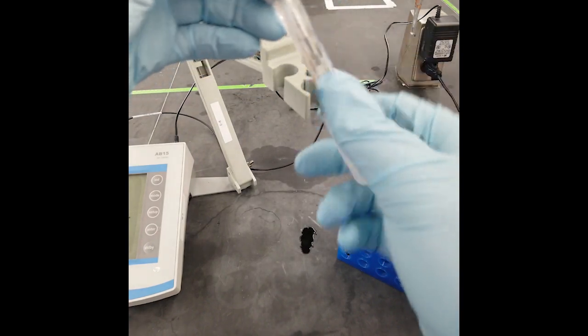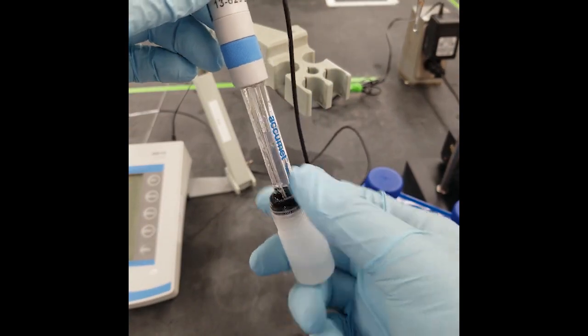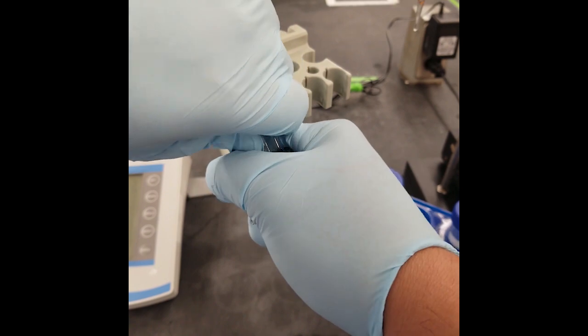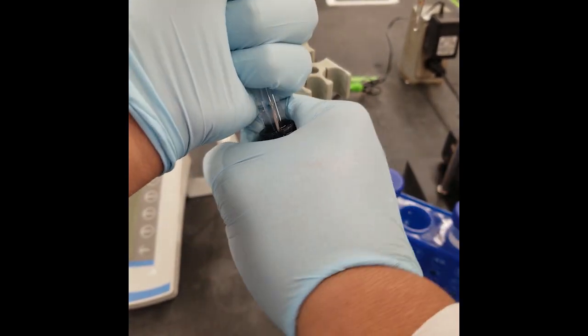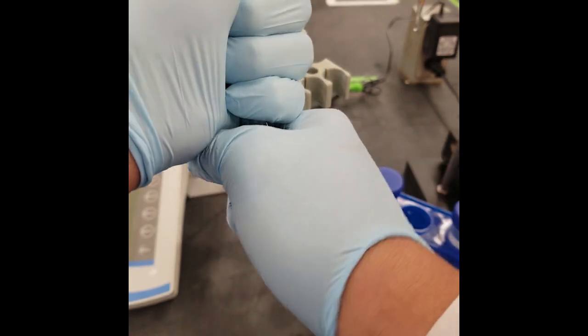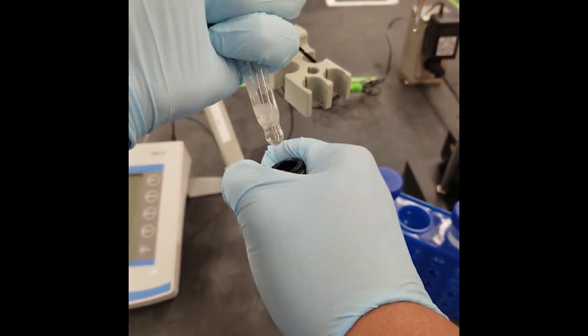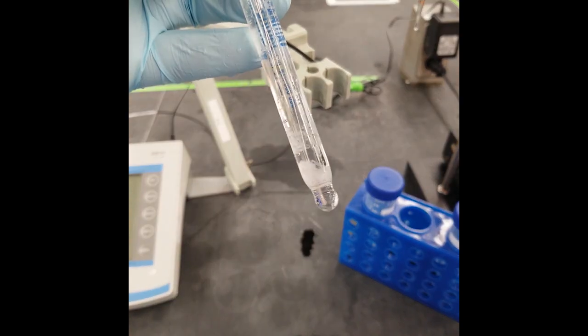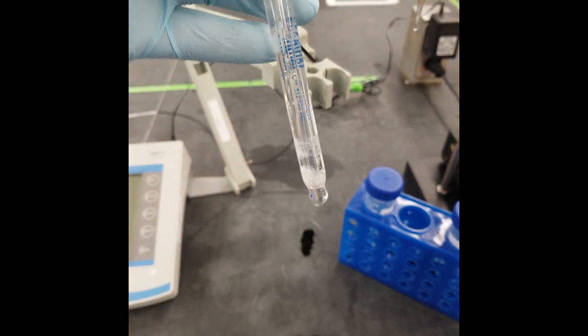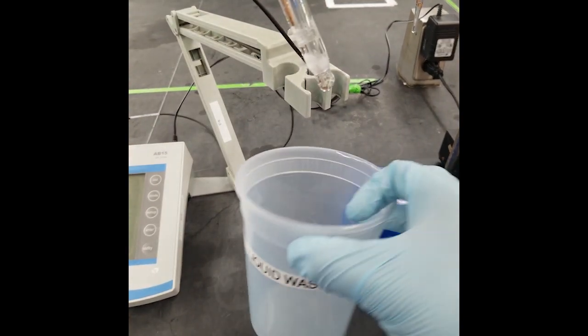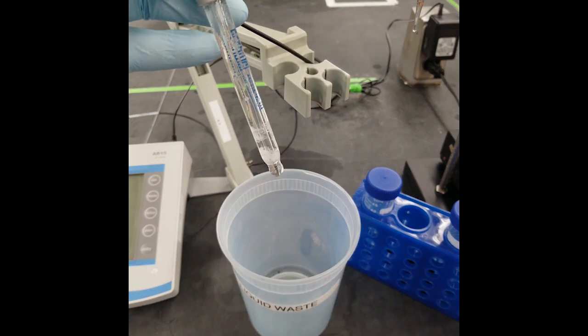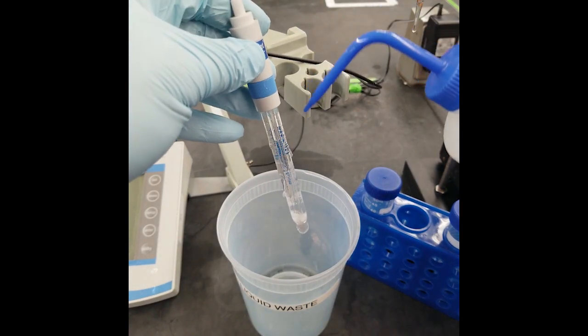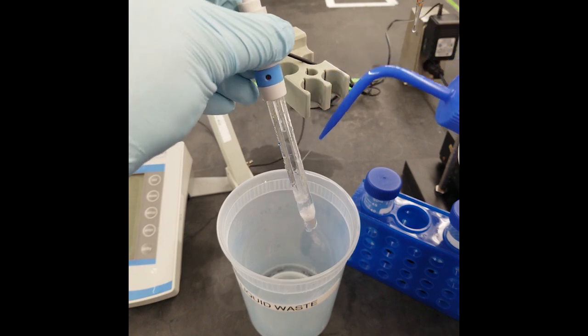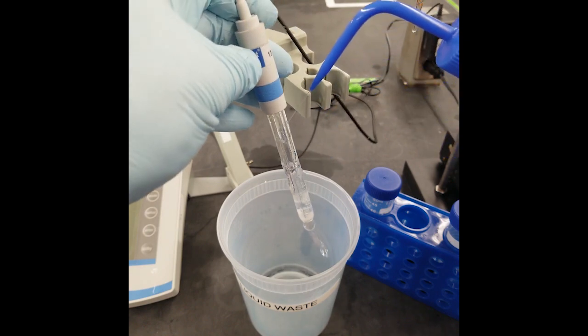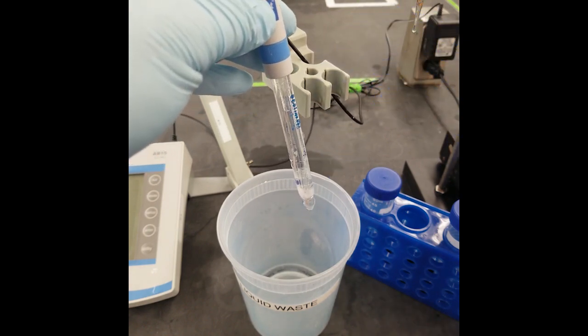So when you're ready to use the probe, you are going to grab both the probe and the storage solution bottle, hold it tightly, try not to apply too much pressure, but while you're doing a twisting motion, pull your hands apart so that you can safely take the probe out of the storage solution. And then immediately you're going to rinse off the storage solution buffer that the probe was covered in by using a DI water squirt bottle, and just rinsing that over your liquid waste container.